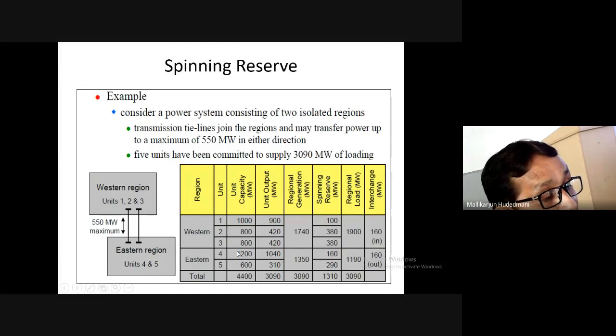See to it that if there is a loss of the 1040 megawatt generator in B, this is lost. I cannot meet the requirement. You can see here 1040 megawatt which is being produced from the fourth generator. Even though I have a generation of 420, if I make it run at full capacity, 1000 plus 800 plus 800, I will be having 2600 megawatt generation from this area. If the load is 1900, the remaining power I can pump here, but I have a limitation of transmission. I cannot fulfill the loss of the fourth generator in the interconnected operation by spinning reserve energy.